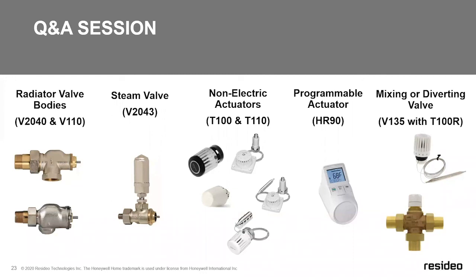And then I've got, you show valves on convectors. In my area, most cast iron units have supply and return coming from the floor. Will this make a difference? No, not really. As long as you have room to cut a valve in, you can make that happen. So as I showed in some of those selection images, the one thing you want to keep in mind is you don't want to install the actuator vertically. So if you get into a spot where, let's say, it comes up from the floor and then shoots over directly 90-degree into the radiator, if it's on the floor where you don't want an actuator, you could always run it up the wall and do a wall-mounted actuator instead.